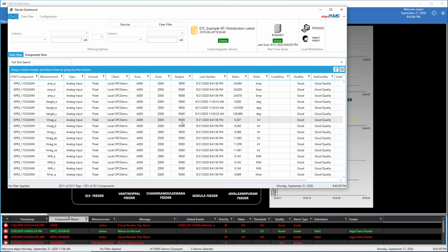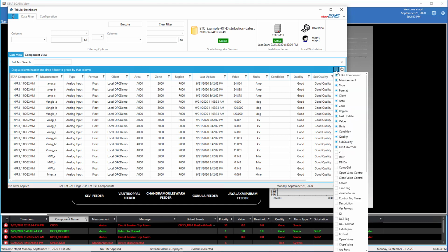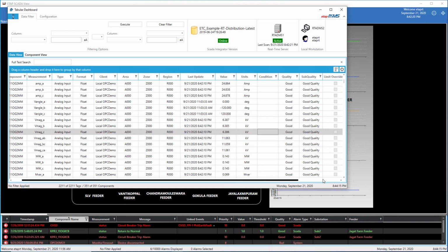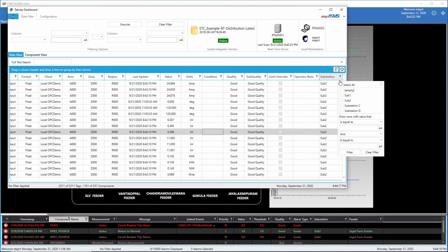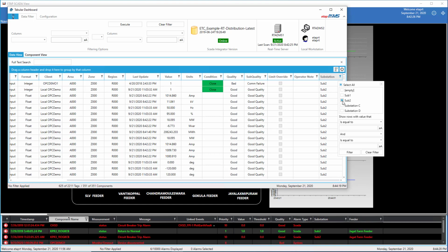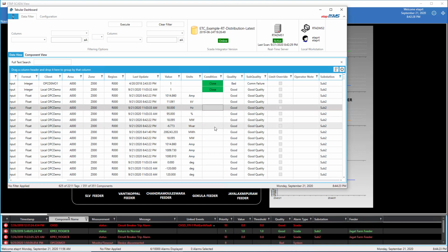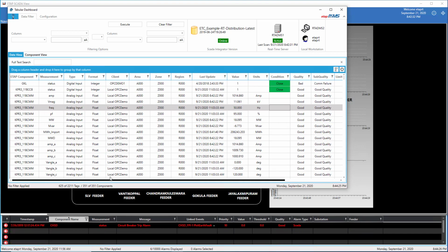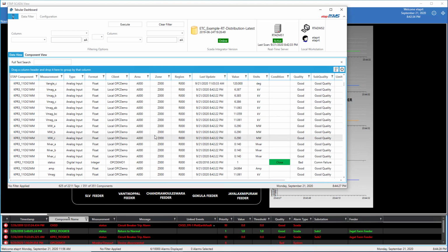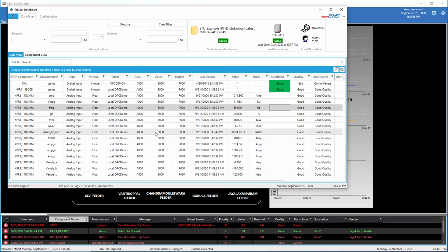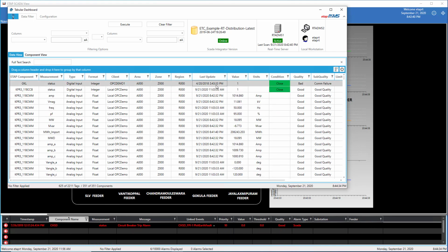Now this information can be filtered. Remember, here we're looking at two substations. I can bring in a substation column, for example, display it on my viewer, and then filter out anything that I don't want to see. So if I only want to see substation 2, I can filter out anything else and look at substation 2. So it's a very nice tool to troubleshoot, to look at the system and see what's communicating and not communicating. For example, here I see that there is a problem with one of the breakers.